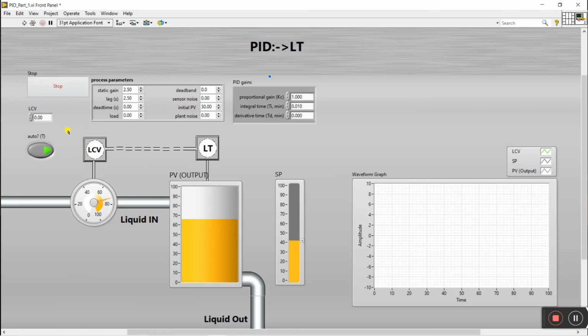I already explained this in a paper, and it's the same as this. This is our PV, this is the set point. This is our LT, liquid transducer, which has one probe that gives the signal to the LCV. With the help of feedback, it sends the value and opens and closes the valve as per requirement to maintain the level. Now let's try to run it.